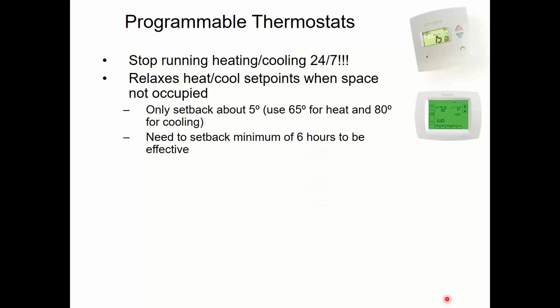So programmable thermostats, this is pretty much a no-brainer. Stop running stuff 24/7. If you run it all night long when you're not there, it's a waste of energy. We want you to relax your set points at nighttime or whenever people are not there. My normal recommendation is to get at least a 5-degree setback. So if you normally heat your building to 70, let it set back to at least 65 at night. You might be able to go lower.